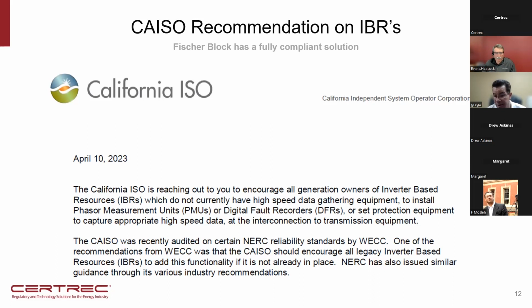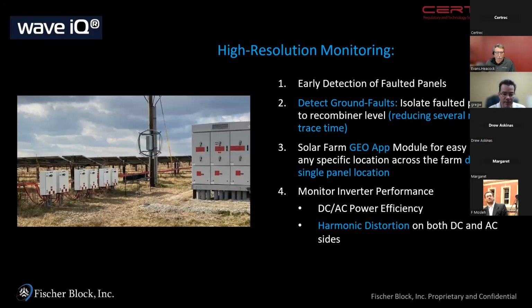And so not only when the plant goes offline, but when there are events out on the grid and the plant does not go offline, if you have a system like ours that's doing 24/7 recording, then the owner operators of those plants will know what margin their plant had. Did it almost go offline, or was there sufficient margin where they're covered so that they can go to sleep well at night? There's confidence that it's meeting the standards. So yeah, that's a big part of what we do. Back to the regulator or the ISO in this case, we can say that we're okay and we can prove that we're okay. So yeah, it saves money, either from trying to figure out what your problem is or to show that you're fine and have the margin like you just said. That's very important. Correct. Yeah.